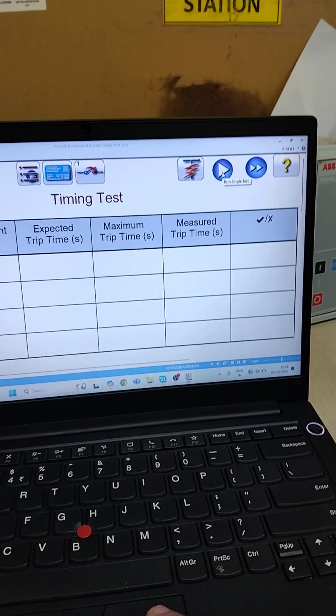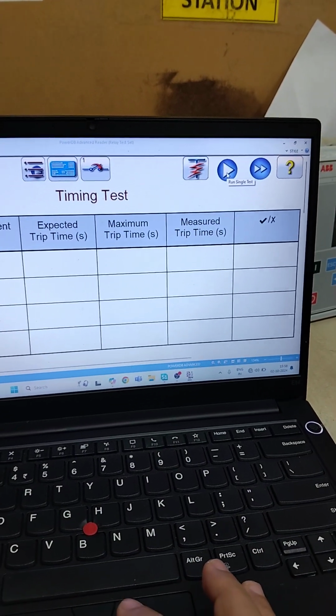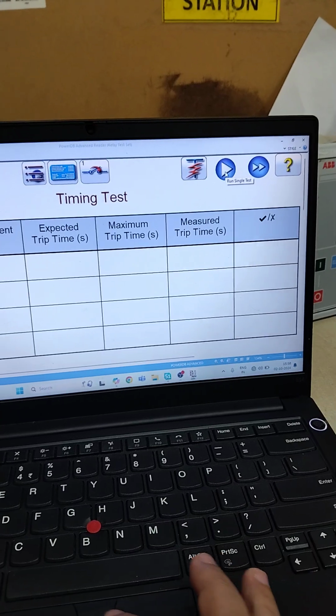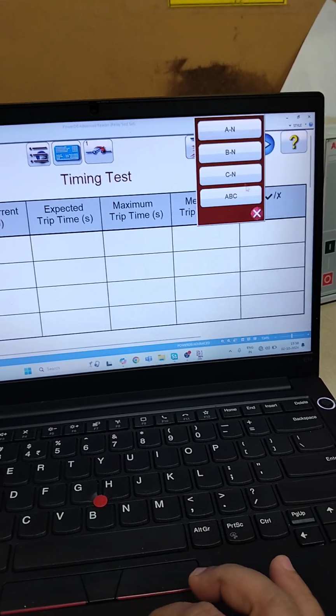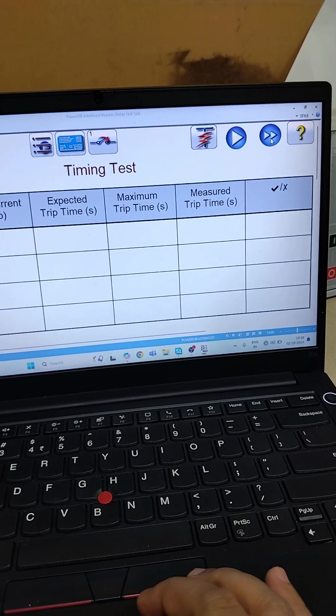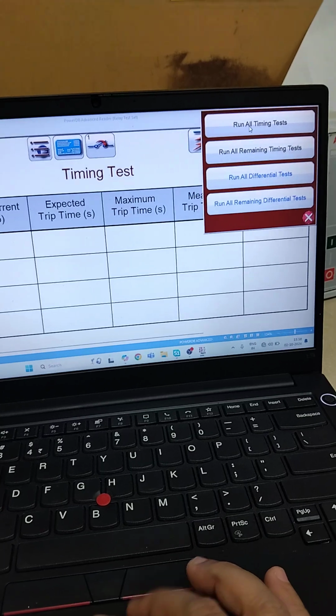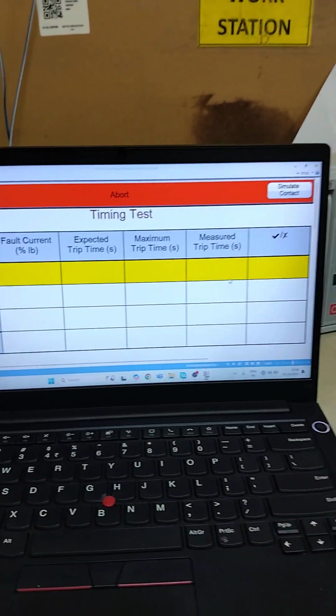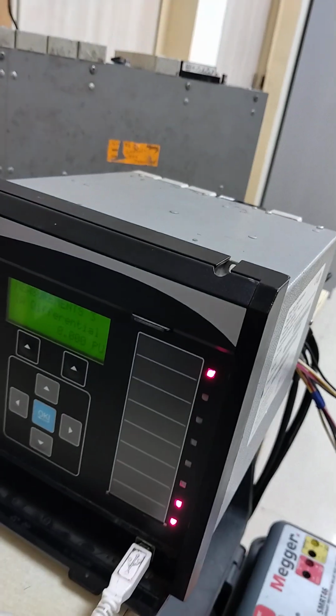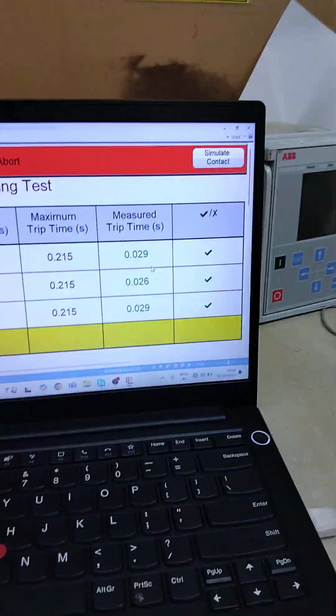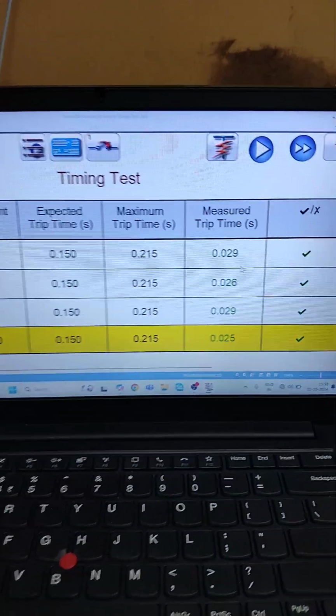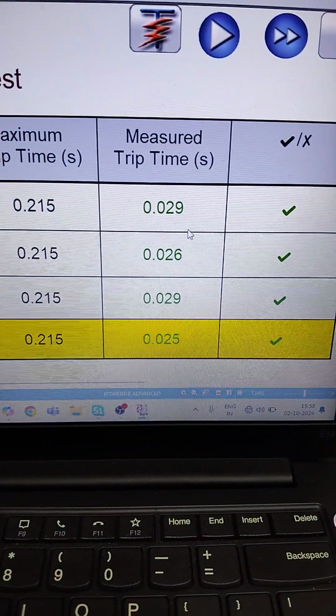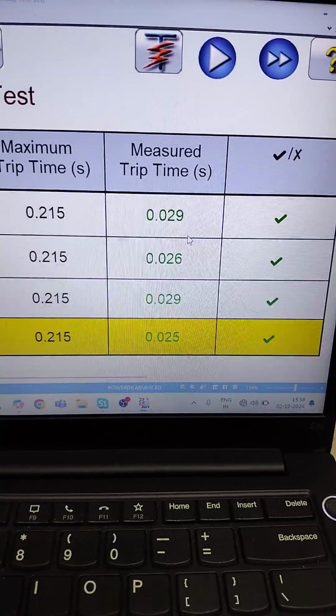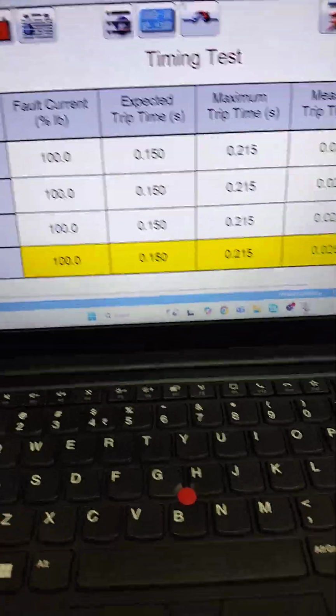In this the kit will inject some differential current, and based on the output it will just check the trip output. So we can check this for all. So you can see that LED 1 is glowing continuously and the kit is injecting, and the timing has been recorded as almost 30 ms, less than 30 ms for all the conditions. Similarly, there is a pickup test.